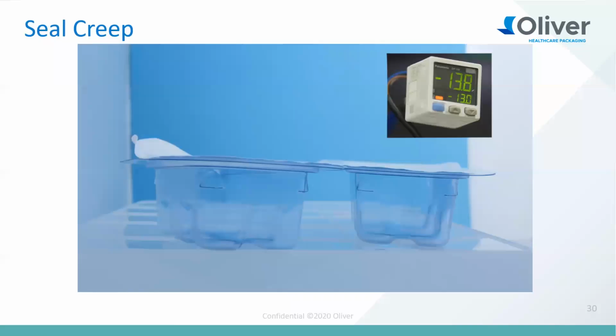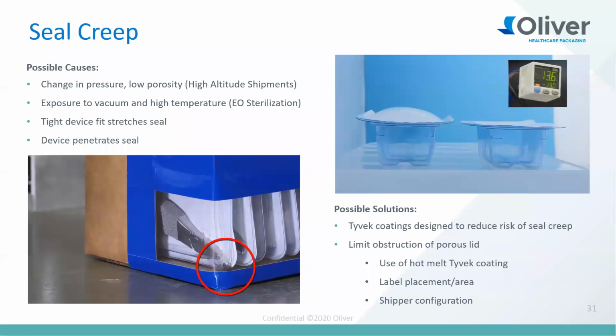Annika, if you can go to the next slide, just so I can talk a little bit about seal creep. I think it's very important. Again, the possible causes: change in pressure, low porosity, high altitude shipments. On the right-hand side, we have that package inside of a high altitude shipment, showing it could have an effect there. Exposure to vacuum and high temperature in the EO sterilization chamber, like we talked about. Keep in mind, it's not only happening there. A tight device fit could also stretch the seal. If you're underpackaging, trying to force a device into a package, it could stretch those seals in a way that looks the same as this.